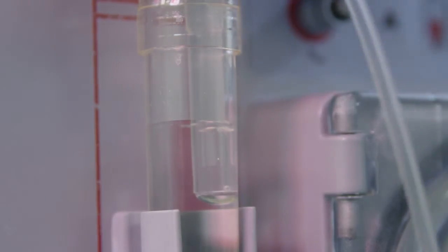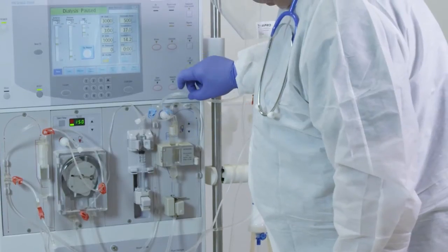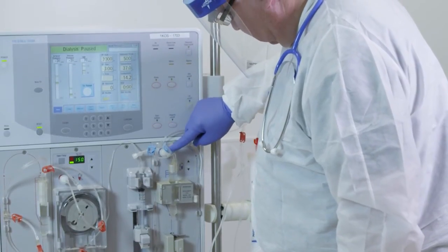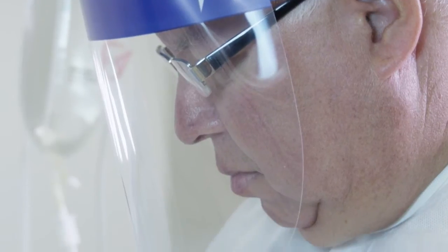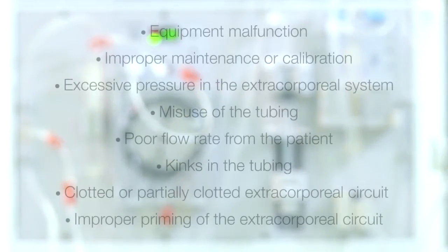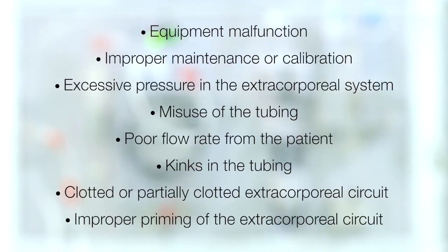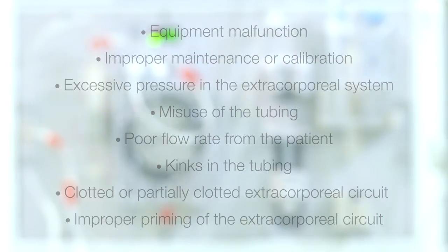Maintain the drip chambers 3/4 full. This will reduce the chance of fluid backup into the monitoring line and will ensure proper monitoring of the arterial and venous drip chambers. Monitoring line backup may be caused by any of the following: equipment malfunction, improper maintenance or calibration, excessive pressure in the extracorporeal system, misuse of the tubing, poor flow rate from the patient, kinks in the tubing, clotted or partially clotted extracorporeal circuit, or improper priming of the extracorporeal circuit.